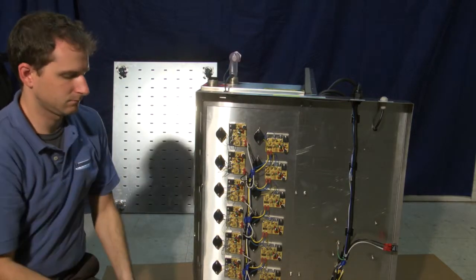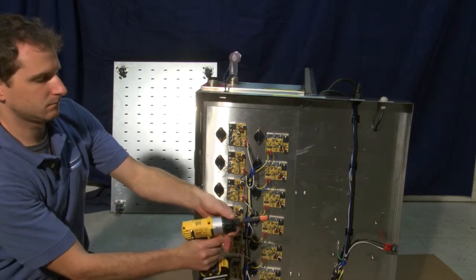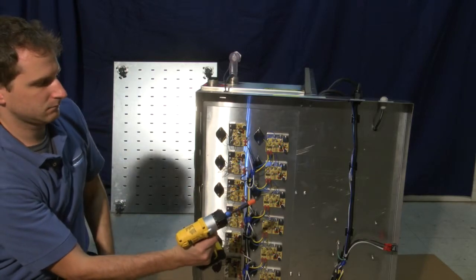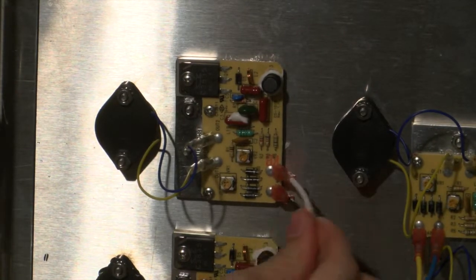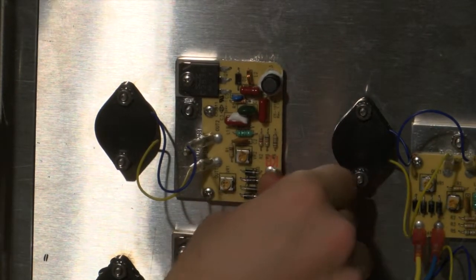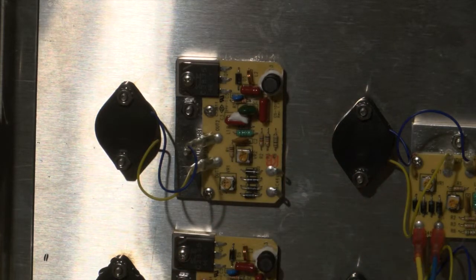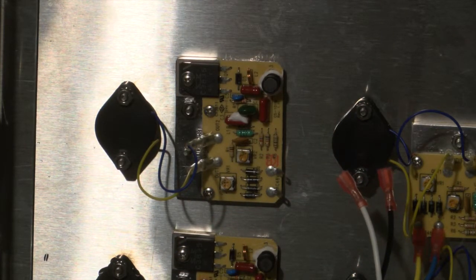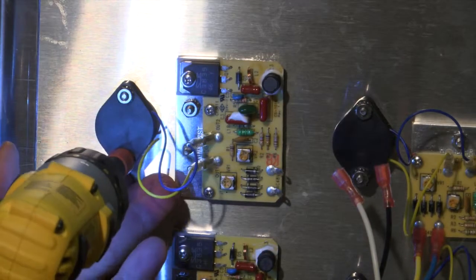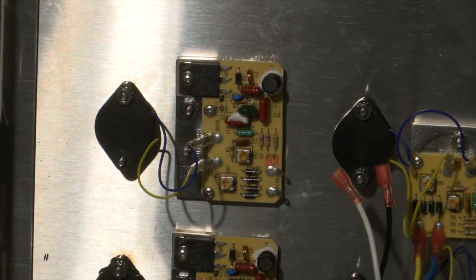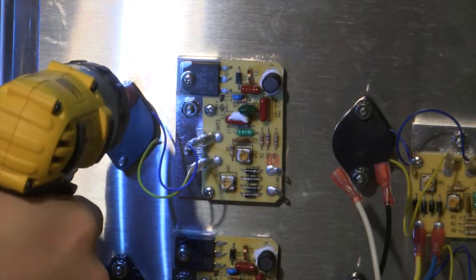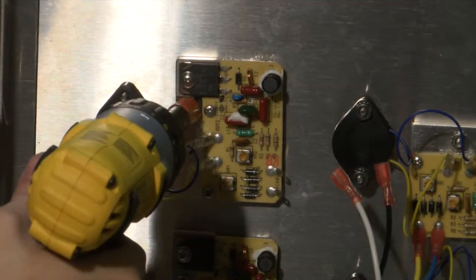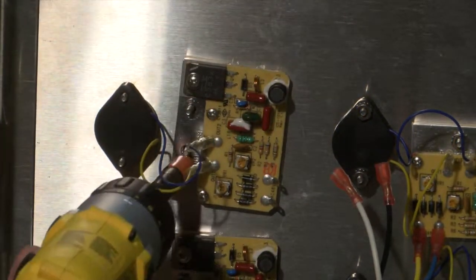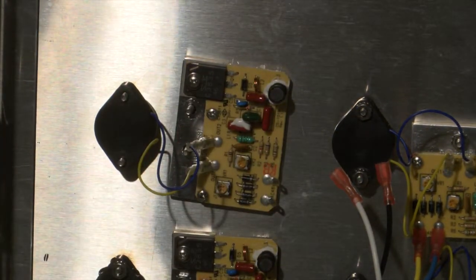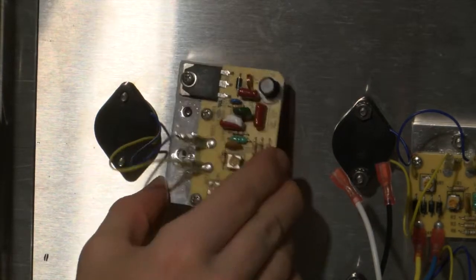You will need a number 6 socket to remove the transducer and circuit board. If you're using an electric driver, have it set at about torque 4. First, remove the 2 daisy chain wires from the circuit board, and then you can remove the transducer and circuit board. Simply unscrew the 2 screws that hold the transducer on, and the 2 screws that hold the circuit board on. You can then remove the circuit board and transducer completely.